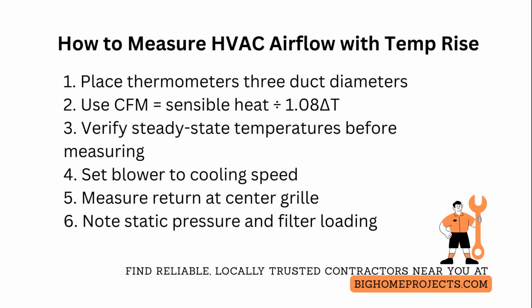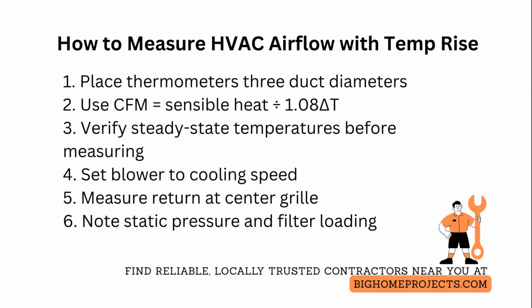For electric heat, convert kilowatts to British thermal units by multiplying by 3,412 and then divide by the temperature rise times 1.08.